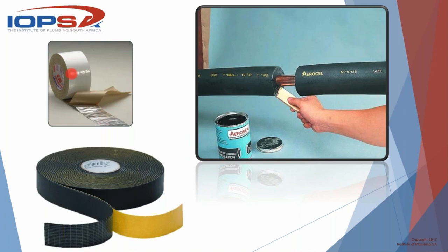If you're using rock wool or anything like that, this self-adhesive foil tape is also the same thing. Every 200 millimeters, you can wrap around that rock wool twice, or use binding wire, whatever the manufacturer requires. There are many ways that we can do it, and it's all doable, and it's all relatively easy.